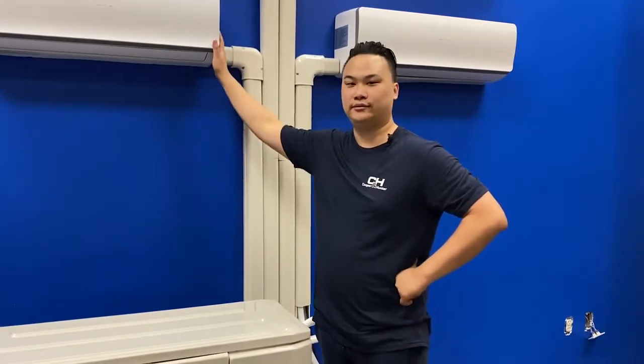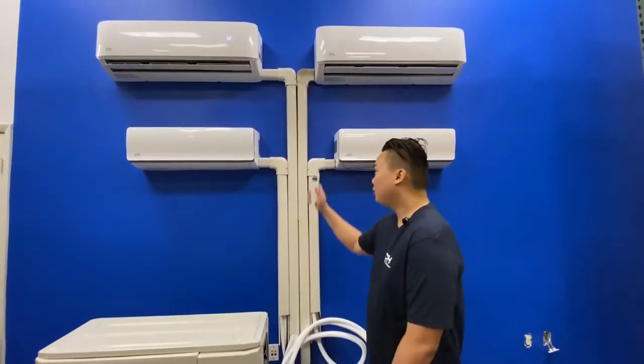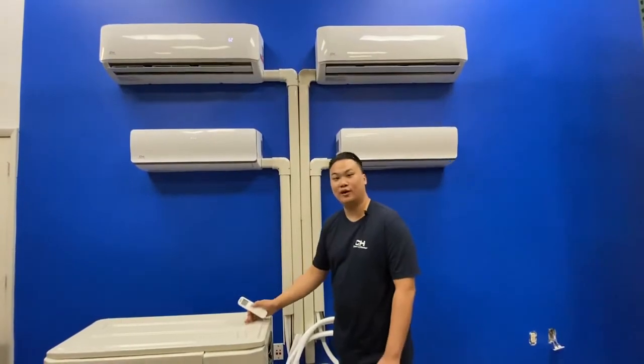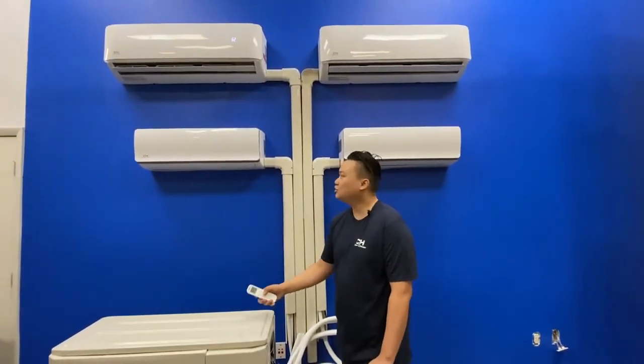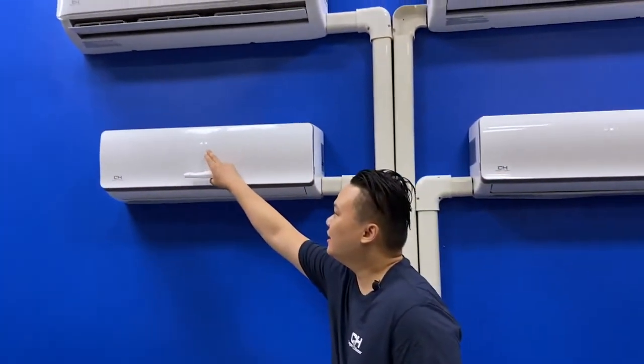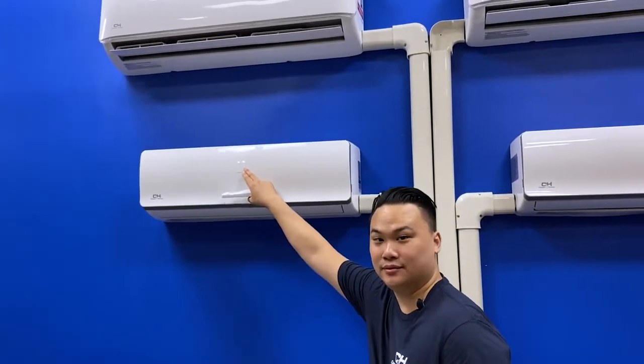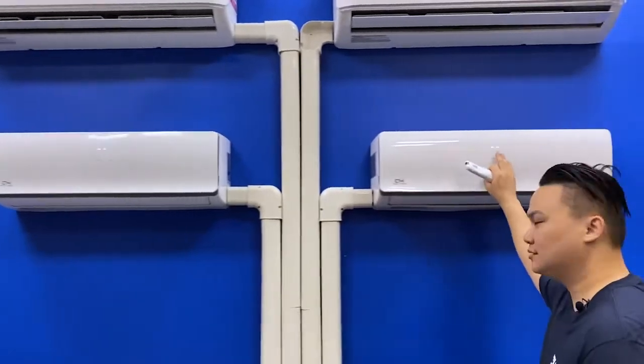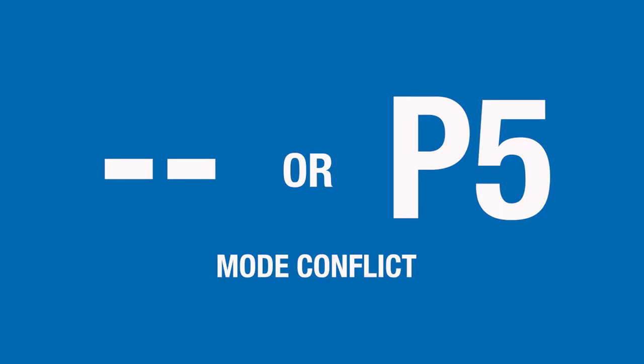or your indoor head. Here we have a multi-zone system. We have 3 evaporators connected to 1 outdoor condenser. As you can see, there is a -- error code on 2 of these units. A -- error code indicates mode conflicts.